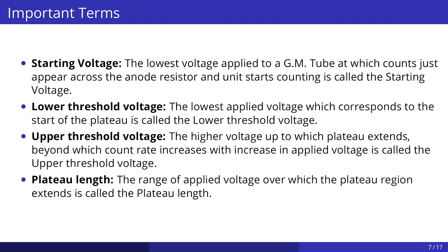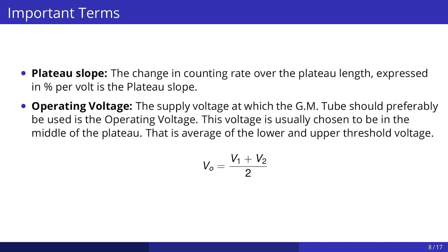The lowest voltage applied to a GM tube at which counts just appear across the anode resistor and the unit starts counting is called the starting voltage. The lowest applied voltage corresponding to the start of the plateau is called the lower threshold voltage. The higher voltage up to which the plateau extends — beyond which count rate increases with applied voltage — is called the upper threshold voltage. The range of applied voltage over which the plateau region extends is called the plateau length. The change in counting rate over the plateau length expressed in percent per volt is the plateau slope. The supply voltage at which the GM tube should preferably be used is the operating voltage, and this is usually chosen to be in the middle of the plateau — that is, the average of the lower and upper threshold voltages.